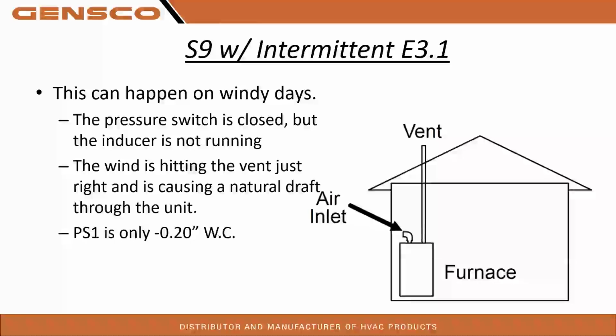Okay, S9 with intermittent 3.1. It can happen. On windy days, typically, pressure switch is closed, but the inducer motor is not running. The wind is hitting the vent, causing a natural draft through the furnace. That PS1 is only a 0.2, so it can happen.